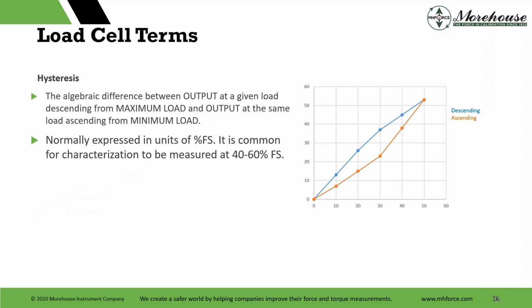Hysteresis is defined as the algebraic difference between the output at a given load descending from maximum load and output at the same load ascending from minimum load. It's normally expressed in percentage of full scale. It is common for characterization to be measured at 40 to 60% of full scale. So you have two curves here, one that's ascending and one that's descending. You're going to take the same point on these curves right here. This is the same point. The error between these, after we plot them both, is what's reported as hysteresis. That's all we're doing there.